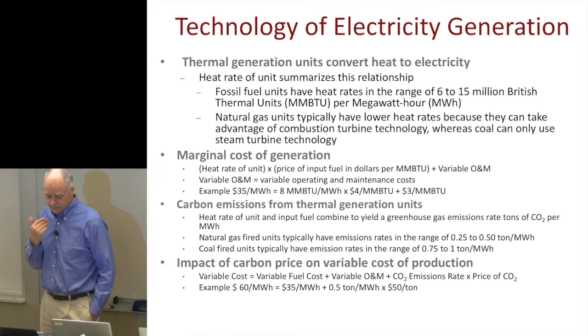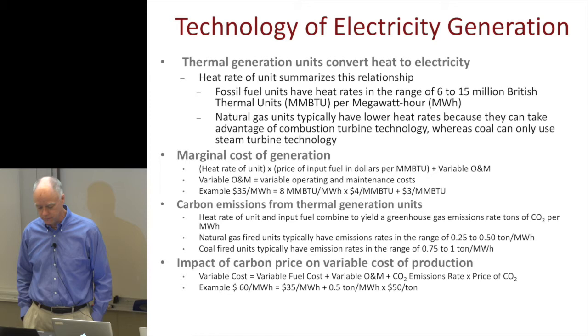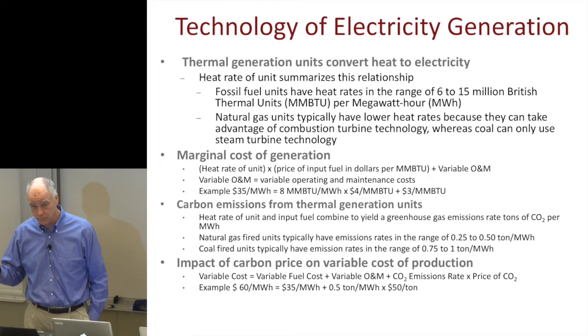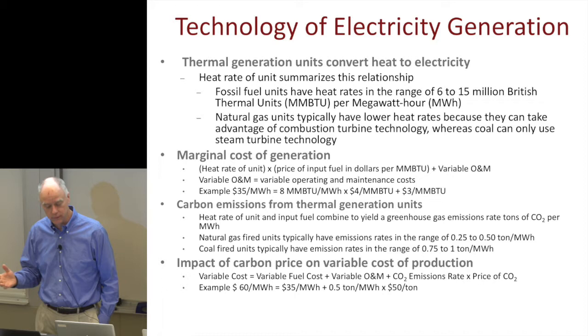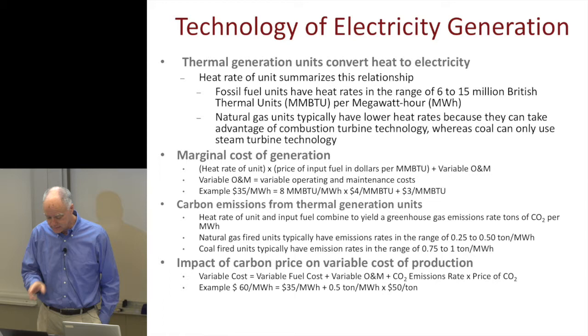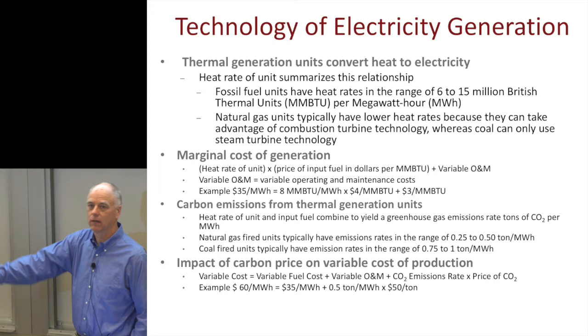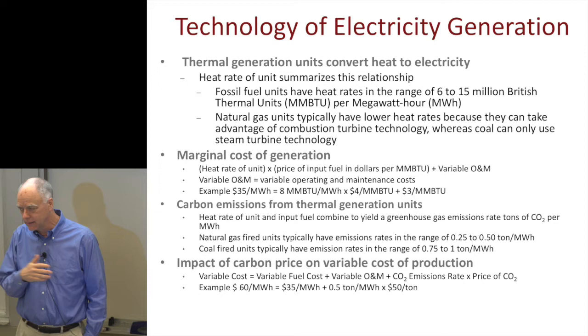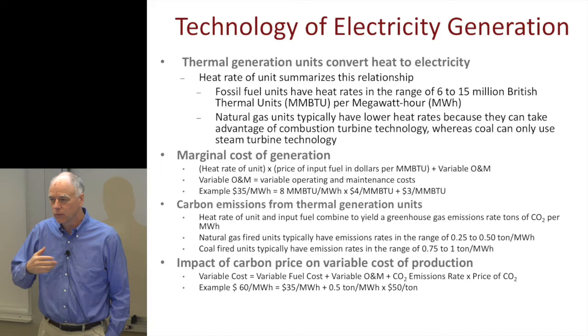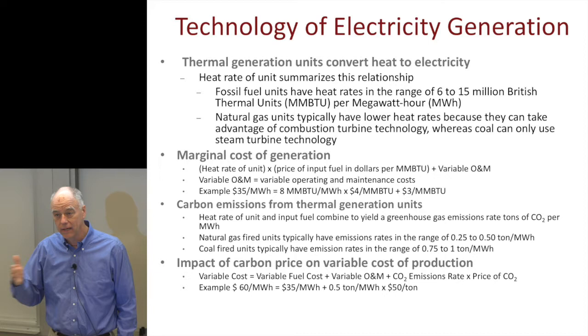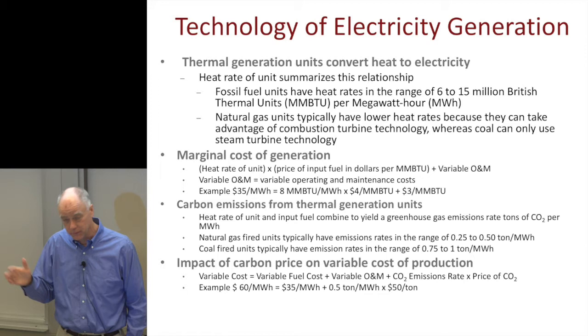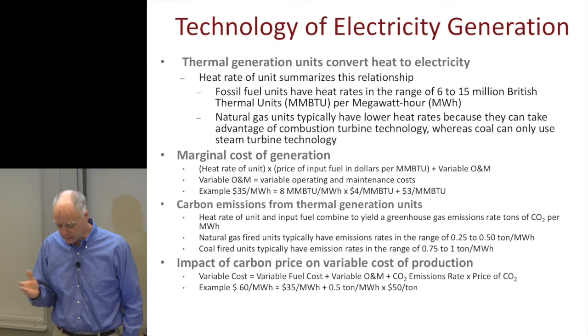The way to think about a thermal generator is you take some input fuel, convert the heat into electricity — either through a combustion turbine or by combusting fuel to heat a boiler, producing steam that turns the turbine. We typically summarize this for generation units using what's called a heat rate, which tells you how many units of heat you need to put in to get one megawatt hour of energy out. The heat rate can vary, much like miles per gallon in a car, but for this game we use a single average heat rate.